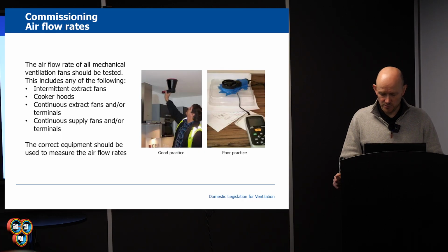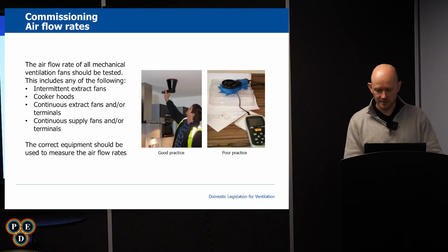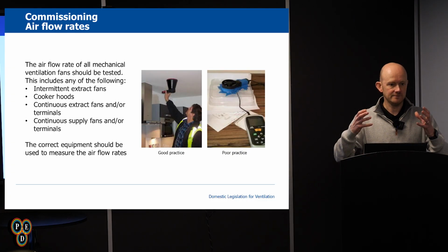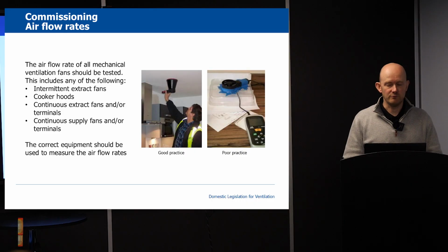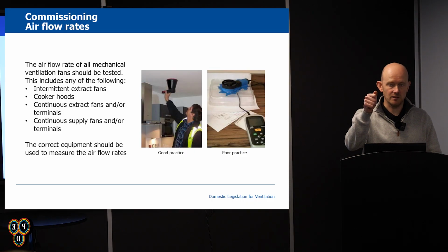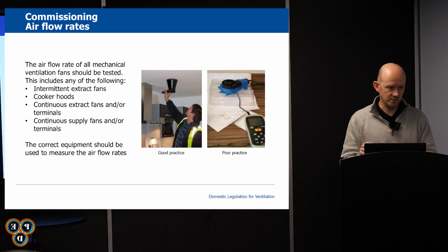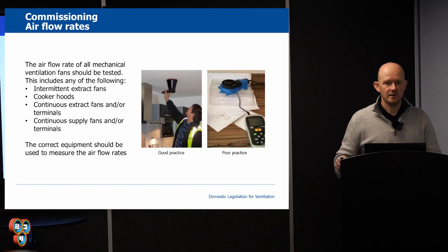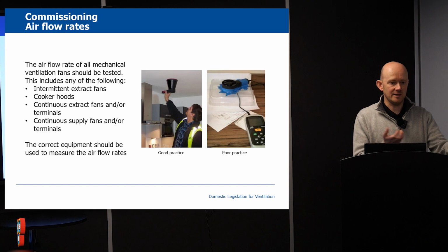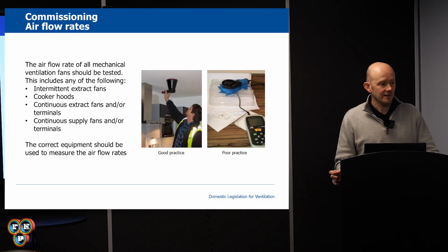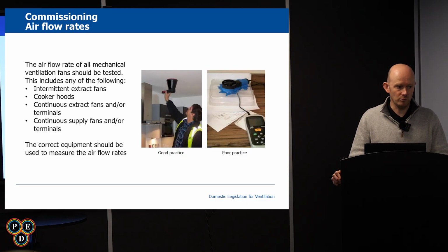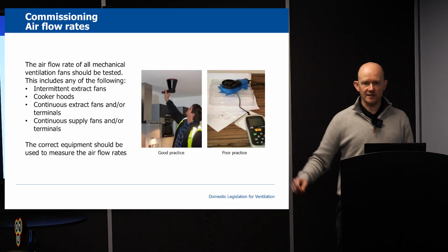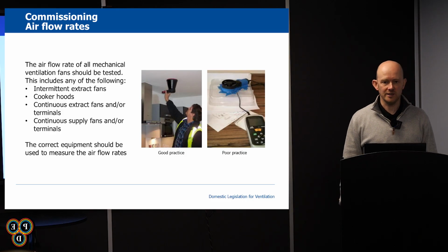Correct equipment should be used to measure the airflow rates, which is an airflow device that has been calibrated in the last 12 months at a calibration centre accredited by UKAS. Anemometers with a hood on it. By regs, every single fan you should be going anemometer, 15 litres a second, signed Joe Bloggs Electrical, submitted. The reality is, when that goes to the homeowner, that's where it ends. There's no building control. If it's under building control, they're getting more and more involved. They definitely will be all over you for this, but the bog-standard fans, there's not enough time in the day to police all of them.